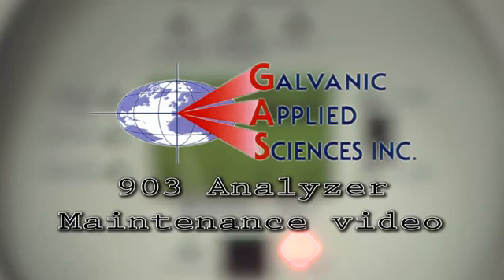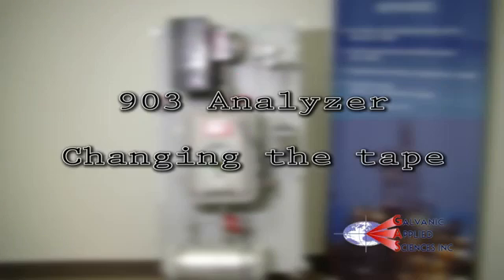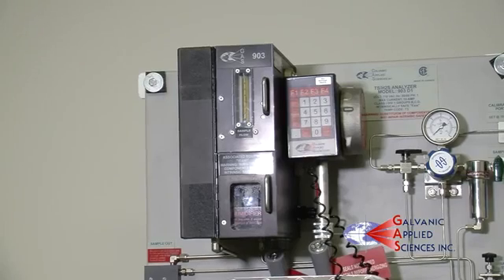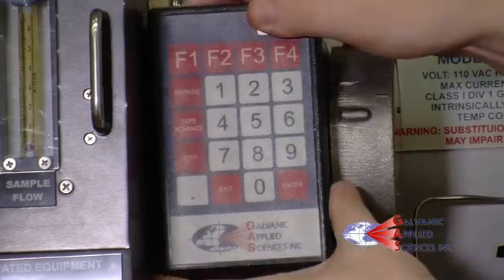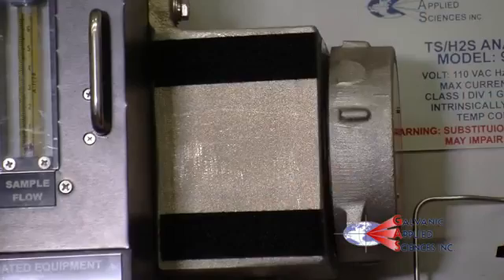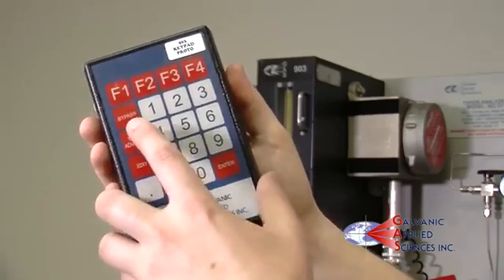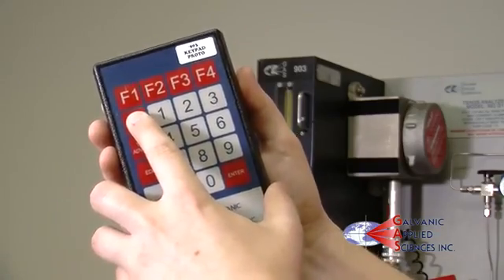Galvanic Applied Sciences 903 Analyzer Maintenance Video: Changing the Tape. Before doing any maintenance, take the handheld keypad for the 903 Analyzer. Press bypass to prevent any alarms from engaging. You will know bypass is activated when you see the flashing orange light below the display.